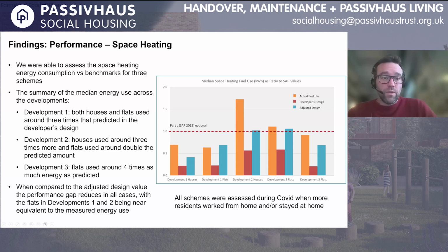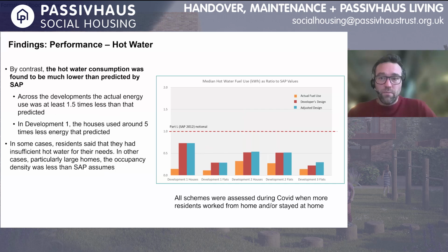I'll pull out some things about space heating. There was a significant performance gap, between 2 and 4 times worse than predicted. You can see actual fuel use in orange, the developer's design predictions in red, and our adjusted design based on site findings in blue. By going to site more often, noting the changes, and modeling those changes in SAP, or you could use PHPP, you get a much more predictive, better model.